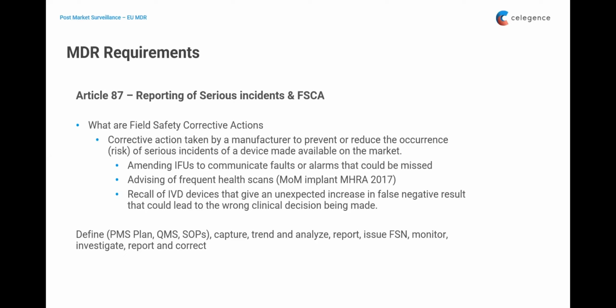I read about this because I think the metal rubbing against each other will release certain cobalt and another metallic component into the bloodstream. It's not poisonous or anything, which was a miscommunication that was out there, but these will show up on blood tests, and it will indicate whether your hip implant is failing or not. So that's one example of a field safety corrective action, trying to tell patients to go for frequent scans. Another is the recall of IVD devices that give an unexpected increase in false negative or positive results that could lead to the wrong clinical decision, okay?